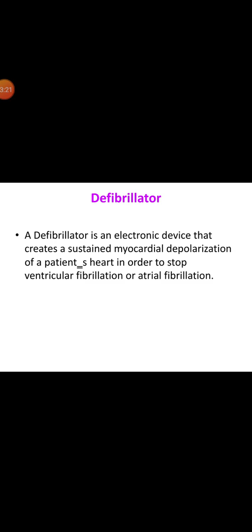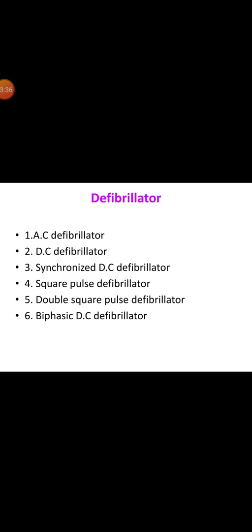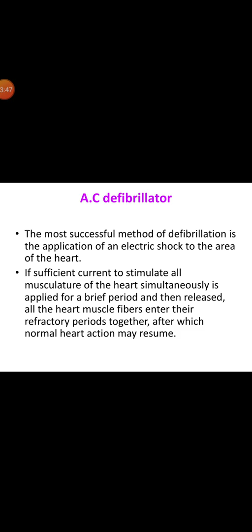A defibrillator is an electronic device that creates a sustained myocardial depolarization of the patient's heart in order to stop ventricular fibrillation or atrial fibrillation. There are many types of defibrillators: AC defibrillator, DC defibrillator, synchronized DC defibrillator, square pulse defibrillator, double square pulse defibrillator, and biphasic defibrillator. In the AC defibrillator, the most successful method of defibrillation is the application of electric shock to the area of the patient. AC defibrillation has some disadvantages.